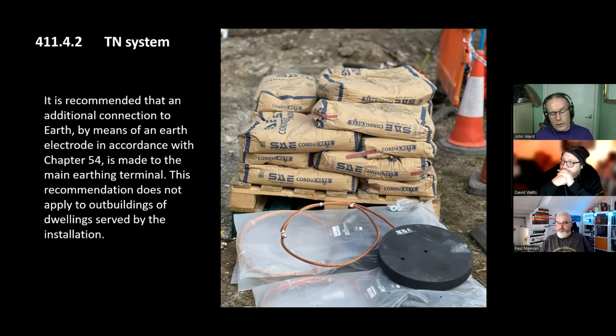In terms of how it works, it's not really different to having the older installations where you had your metal pipes coming in and they were bonded. Although those weren't earth electrodes as such, they were acting as that. But of course, now with plastic pipes and all the rest of it, we don't generally have metal pipes coming in. So this is kind of the replacement for that.